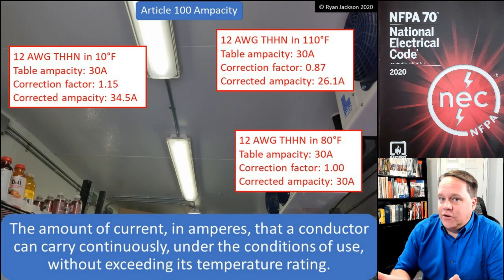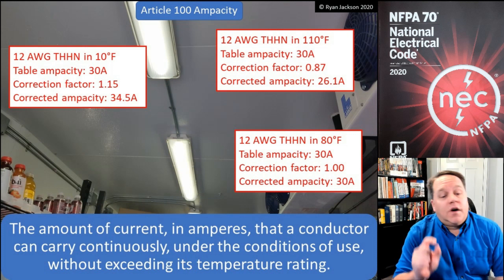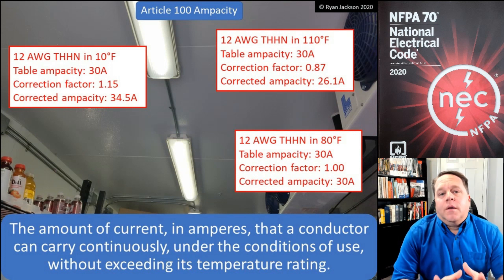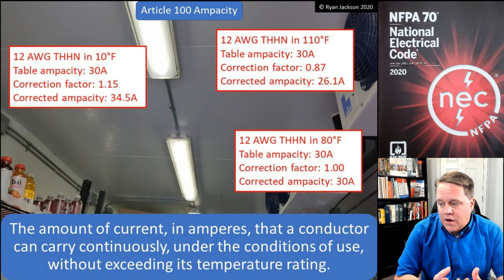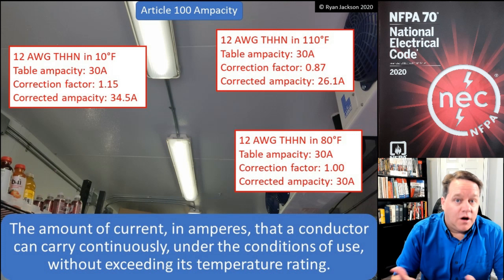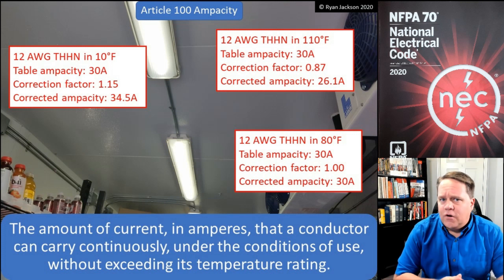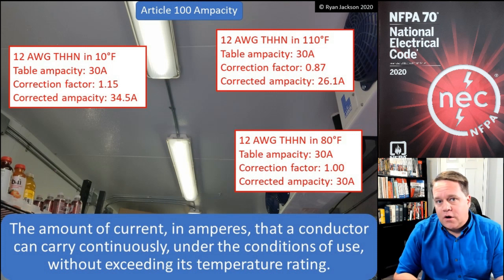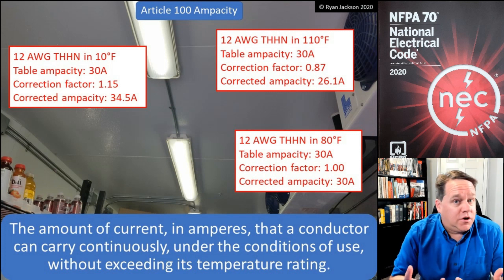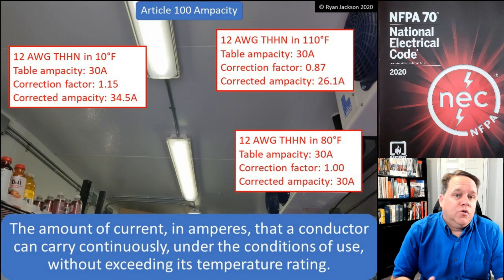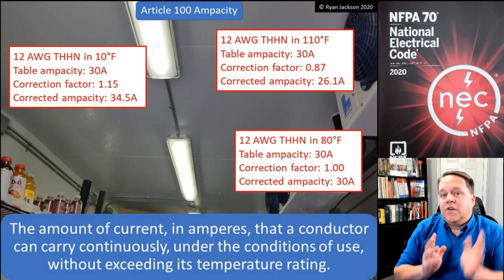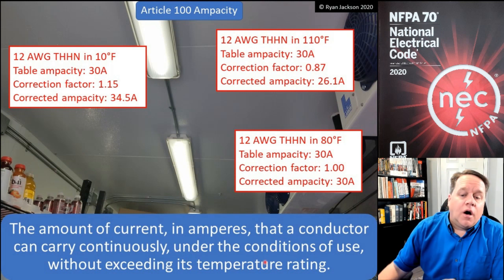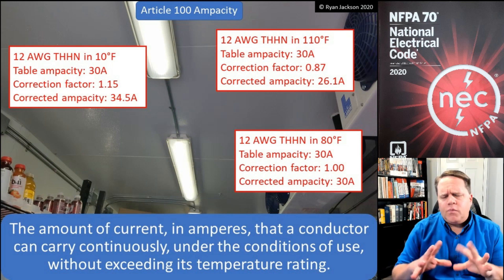Ampacity is measured in amps. That a conductor can carry continuously — so forever. There's not a three-hour limitation. If I have an ampacity of 30 amps or 100 amps, that means I can carry 30 amps on that wire forever. It's not how much current it can carry for three hours or two hours or ten — it's forever. So if it says 30 amps, that means you can put 30 amps on it all day long.